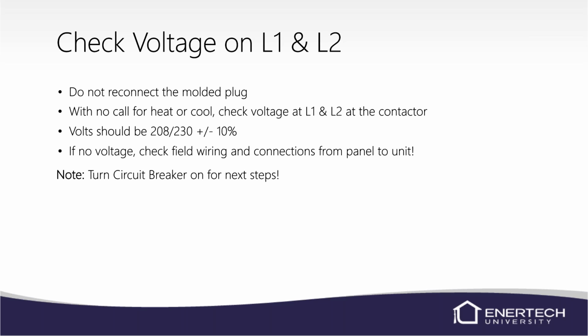So with no call for heating or cooling, check voltage to the contactor at L1 and L2. Obviously, if you have 208 volts, it should be somewhere near there. Same thing with a 230, plus or minus about 10%. If there's no voltage, check your field wiring and check your connections from your panel and check that breaker in the panel. You could have a couple different problems going on. The compressor could have tripped the breaker one too many times and the breaker in the panel is weak. So make sure you're getting power out of the breaker. I've seen that a few times where the breaker's actually bad, put the new breaker on, and then the compressor was probably what caused it, but make sure you check the breaker in the panel as well.